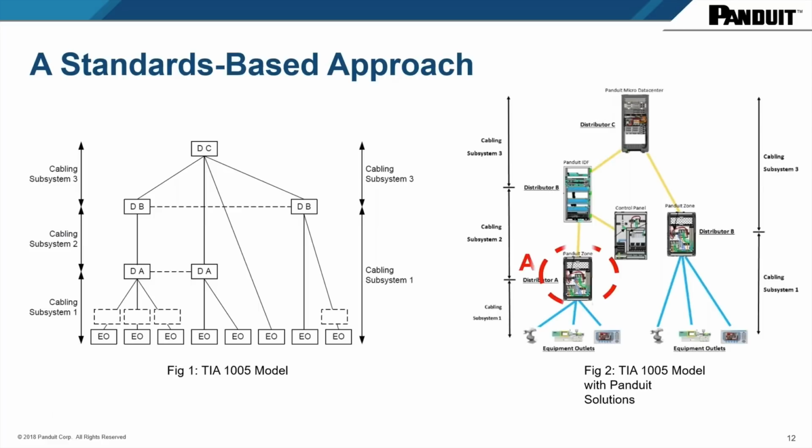And as you start looking at each one of these points, you will find that at distribution A, this is where connectivity is probably at a M.I.C.E 3 category, and you have to worry about that environment. When you go to a B, you will encounter more of a M.I.C.E 2, and you go up to C and you find a M.I.C.E 1 category, where you really shouldn't worry about that environment.